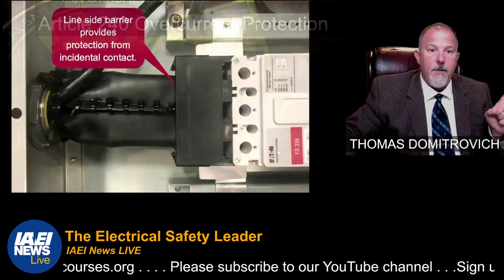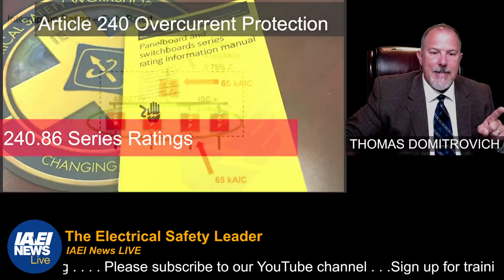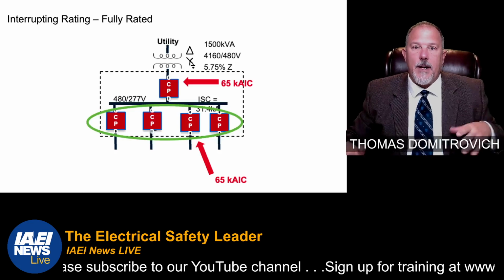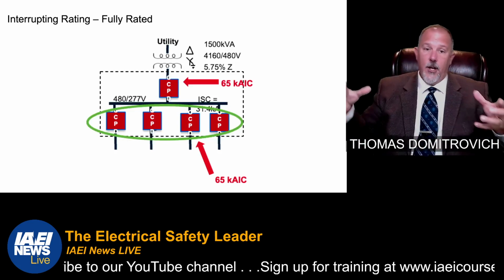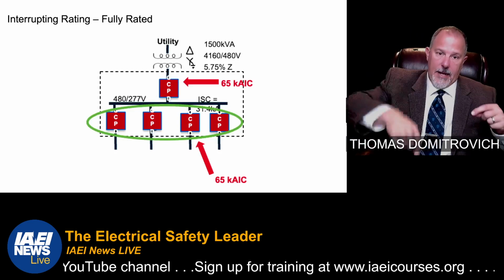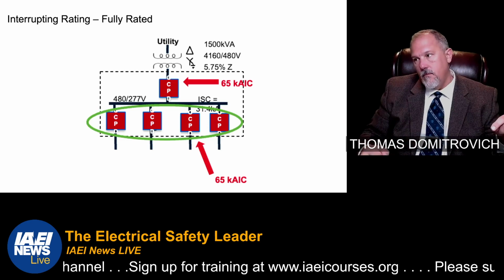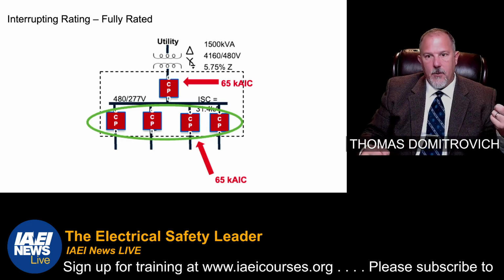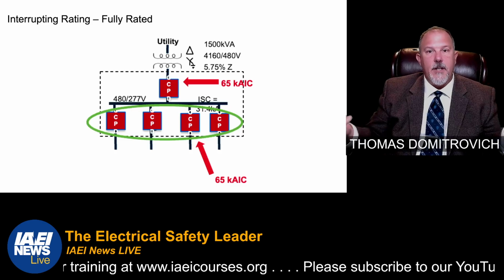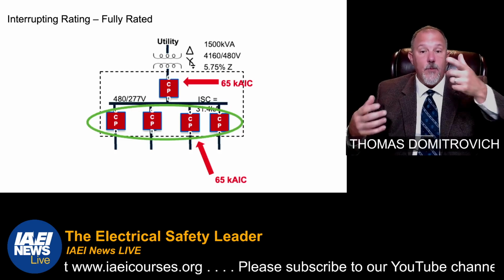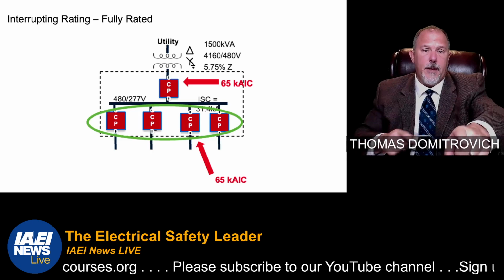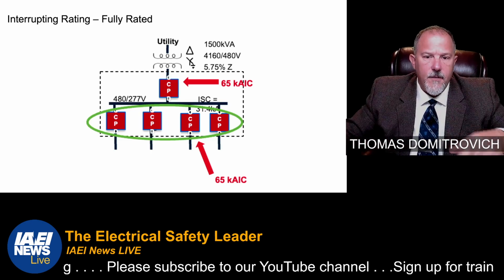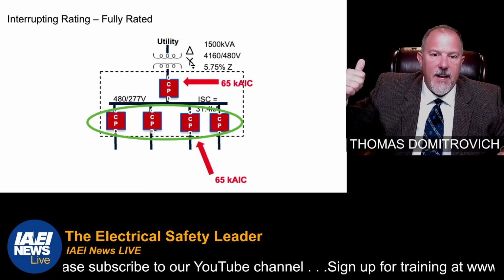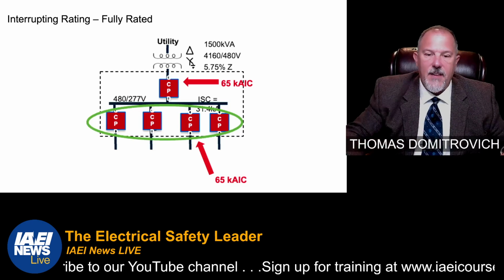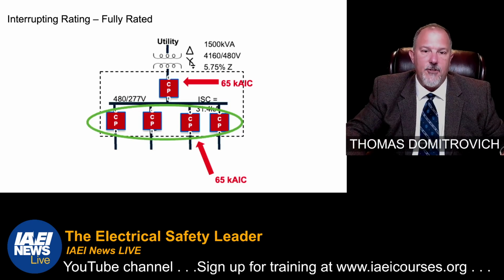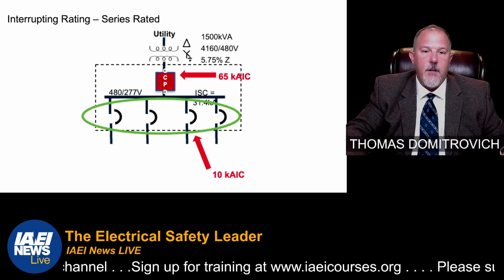All right. Now, another area, 240.86, series ratings. Remember, we talked about the short circuit current rating. What did we say in that label? It's dependent upon the lowest interrupting ratings, or if you have a series rated pair. So what is series? This is a fully rated system. I have a fault current of, say, 31,000 amps. I've got a 65K breaker upstream and a 65K interrupting current breaker downstream. That's a fully rated system.